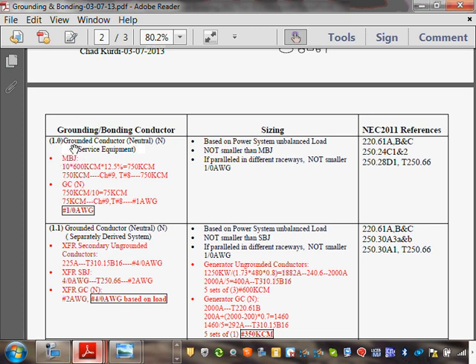So to size the neutral, first I have to size the service conductors. For those of you who dealt with these, I can carry, for 10 sets of 600 kcm, a 4,000 amp switchgear. Okay, how do I know that? You go to 310.16, and it will tell you some sizing. Use the calculator. So that 600 kcm, these are 10 sets. Imagine 10 conduits, 3 phases in each, as well as a neutral, coming to your 4,000 amp switchgear. If it was your building, guys, a 100 amp panel, it will be one conduit with a 100 amp rated conductor coming into it.